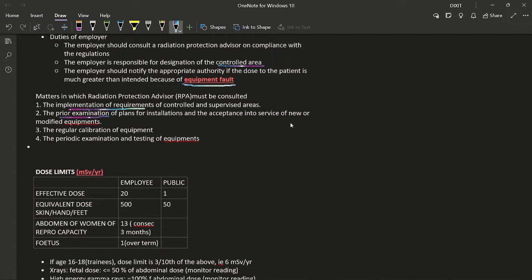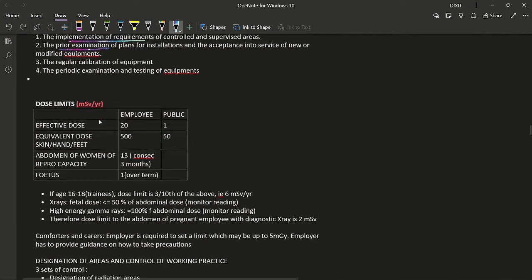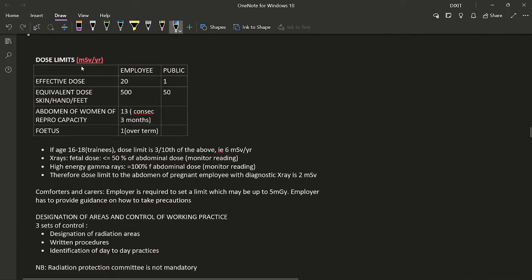The RPA must also be consulted for regular calibration and periodic examination and testing of equipment. Dose limits under IRR 99 are given in millisieverts per year — watch for the unit in the exam. Effective dose for employees is 20 mSv/year; for the general public it is 1 mSv/year.